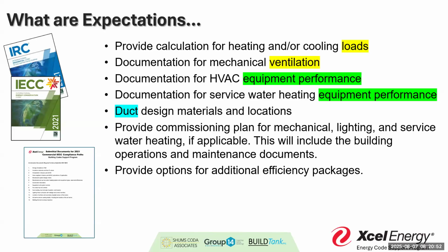When you get into HVAC equipment, the actual equipment - how is it performing? When do we need commissioning? When do I need to have that second person come out and actually make sure the system does what it's supposed to, activates? What do you do when a system requires commissioning that takes longer than you have before you issue a Certificate of Occupancy? Do you issue a temporary? These are conversations that are a little deeper in reality, but also - what is that duct system going to look like, and what are we going to do as far as controls for it?